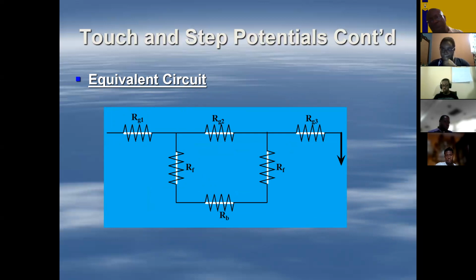What I want to simply highlight is the fact that we have to give consideration to them - that is the key. You have to give consideration to what happens when somebody touches a piece of equipment during a fault, what happens when a person is walking around in the substation during a fault. And of course we can't tell how long or when the fault will occur. We have looked at our relays and how they operate, and depending on the type of fault we still have a few things to look at in terms of protecting the different pieces of equipment. But the reality is, whatever fault it is, it can occur. We have talked about phase to earth faults - they occur, you will have these earth fault currents happening in our system. How do we ensure that people are not at risk?